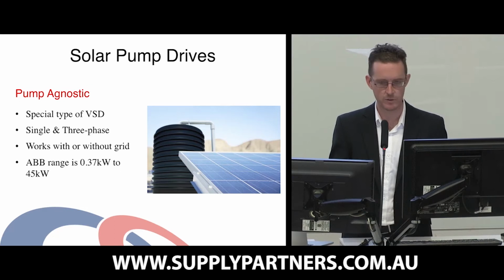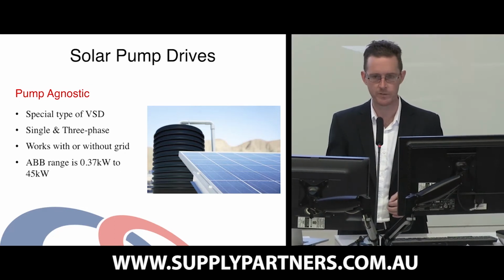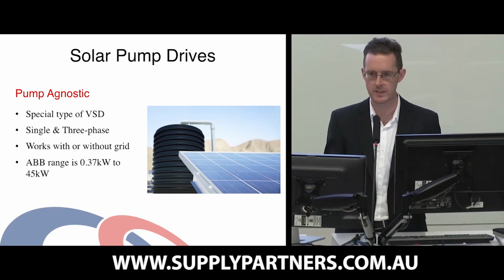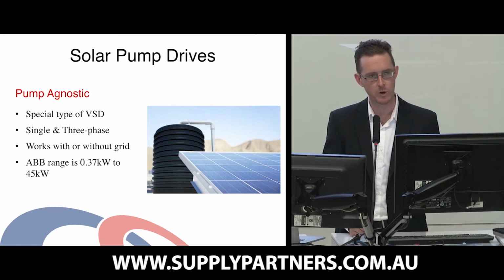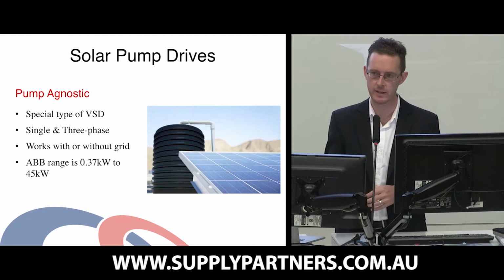In this case, with an ABB solar pump drive, we're using basically a variable speed drive. And ABB is the world's largest manufacturer of variable speed drives, so they definitely know this space well. A variable speed drive takes AC, grid AC at say 50 hertz, chops it up into DC, and then puts it back into AC, but at a different frequency. And solar pump drives allow us to plug PV DC right into the DC bus halfway through there. What this means is it's pump agnostic.